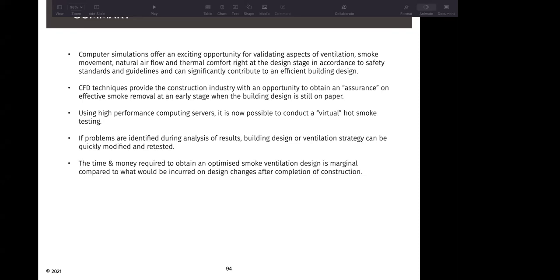Using high performance computing servers, it is now possible to conduct a virtual hot smoke testing. If any problems are identified during the analysis of results, building design or ventilation strategy can be quickly modified and retested. And the time and money required to obtain an optimized ventilation design is marginal compared to what would be incurred on design changes after completion of construction. So basically, it gives you the opportunity to test your design while it's still on paper. You can retest the design if any problems are identified, without having to physically prototype and without having any structure in place.